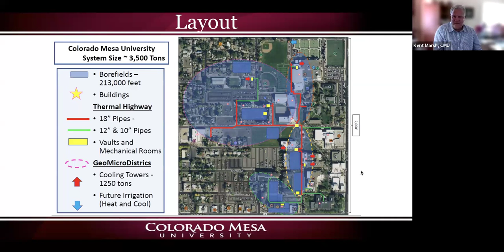So what is a TEN? The basic component of a thermal energy network is what I refer to as a drill field. I'm sure there's a better term for that than what I came up with, but in short, we use conventional drilling rigs to drill a hole, an 8-inch or a 6-inch diameter hole, into the ground. We drill that hole 600 feet into the earth, and we fill that hole with a thermally conductive grout. We then take a piece of pipe that's looped at the bottom, and it's a 1.25-inch diameter piece of pipe, and we attach a weight to the bottom of the loop, and that pipe is pulled 600 feet into the ground.